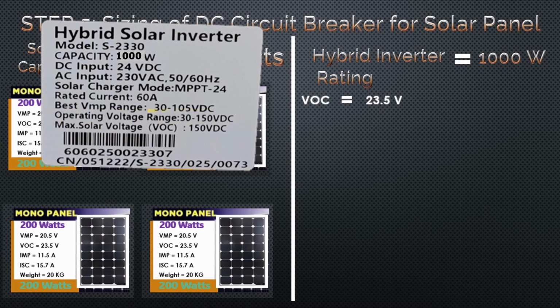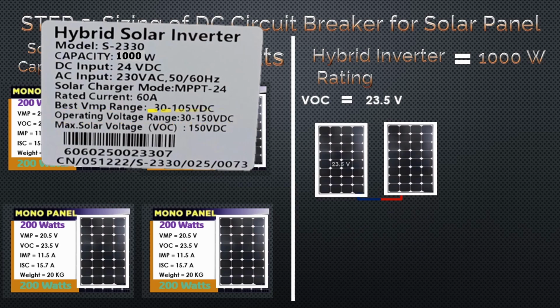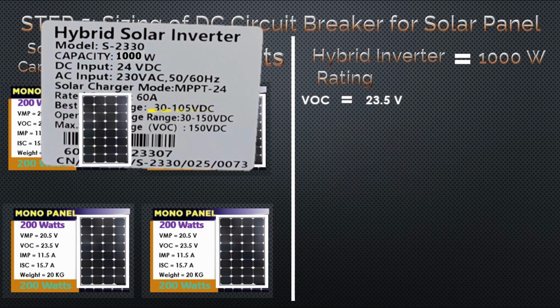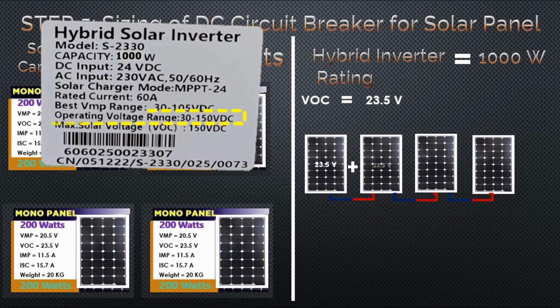So, base sa VOC ng solar panel at DC voltage range ng inverter, may dalawang option ka na pwedeng maging connection ng solar panel na papasok naman sa DC voltage range ng inverter. Now, if you will connect two panels in series, you will add the VOC of two panels, and that is 47 volts. So, it is within the range of 30 to 150 volts. Now, if we will connect 4 200 watts panels in series, you will get 94 volts. And it is also within the range of 30 to 150 volts DC.